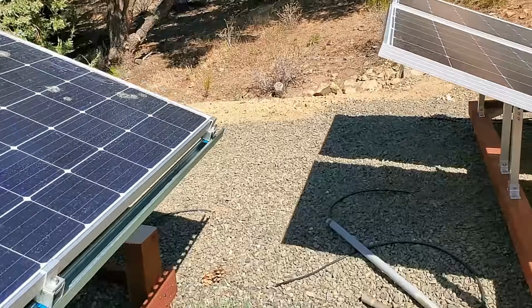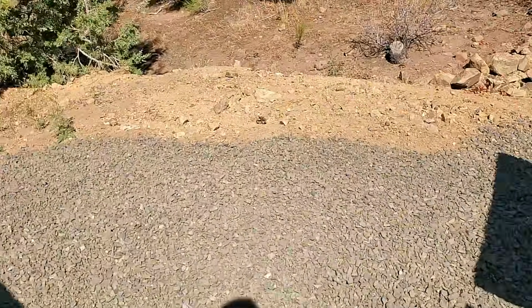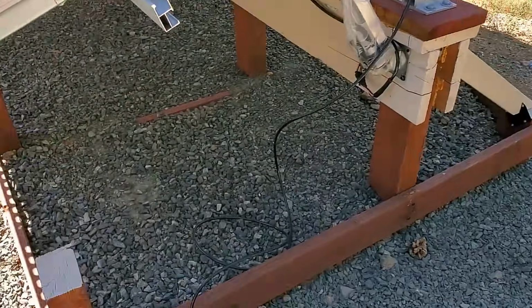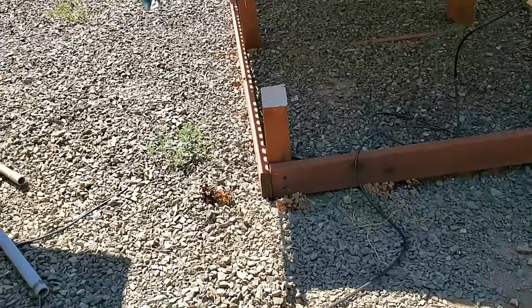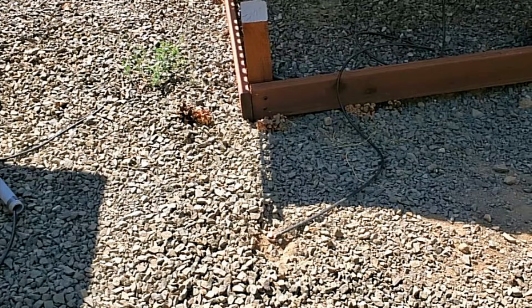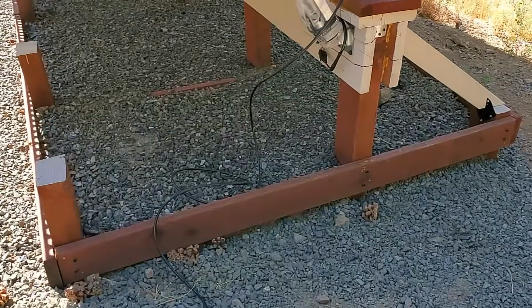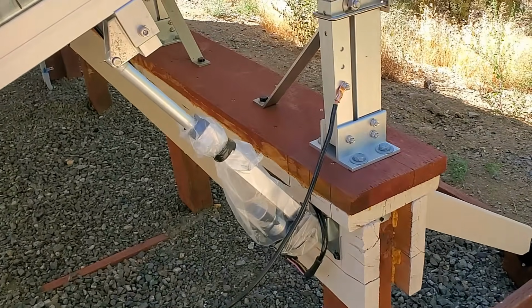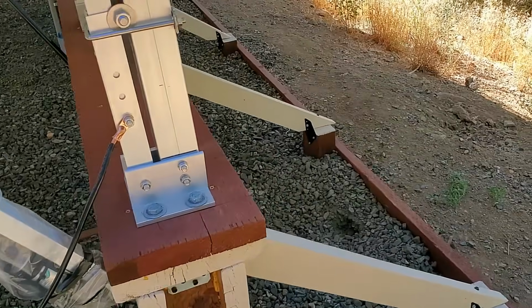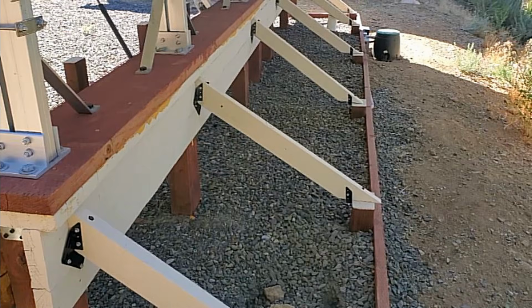As we make our way around to the back of the system, I want to point out a critical safety feature: the 8-foot grounding rod securely attached to the frame of the solar ground mount. This is a code requirement, ensuring proper electrical grounding and overall system safety. Now, looking closely at the rear of the structure, you'll notice the rafter-style braces connecting the main pedestal to the back row of 4x6 posts. These braces, much like traditional roof rafters, are anchored using 8-inch timberlock screws and hurricane ties, providing both structural integrity and resistance to high winds or shifting loads.